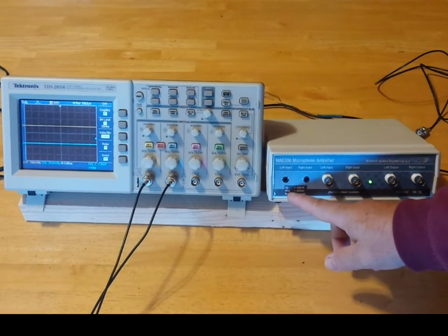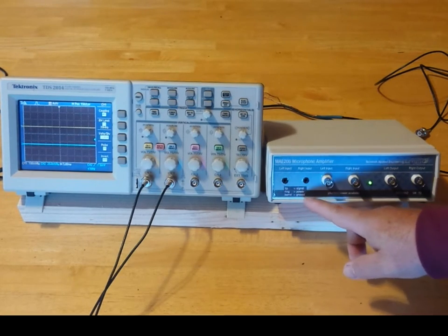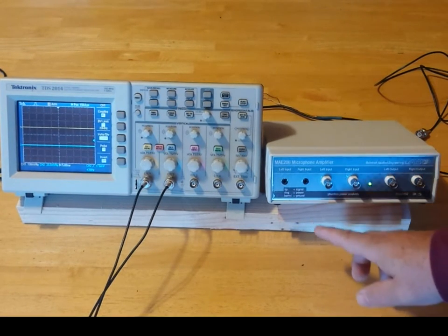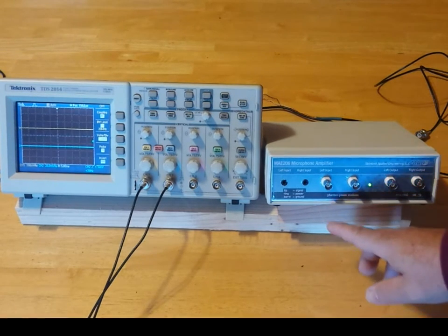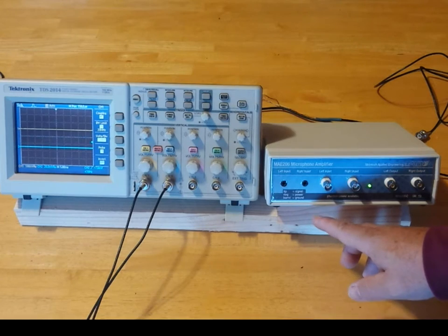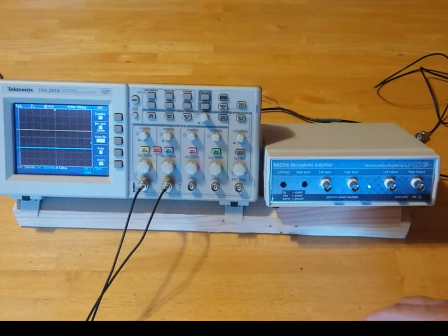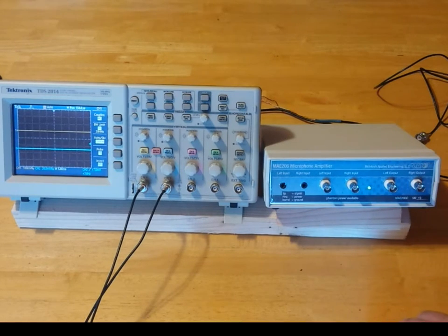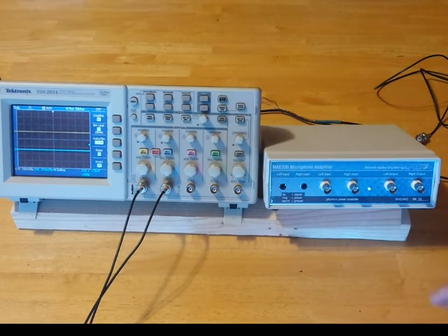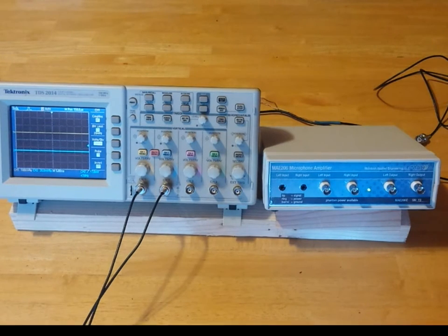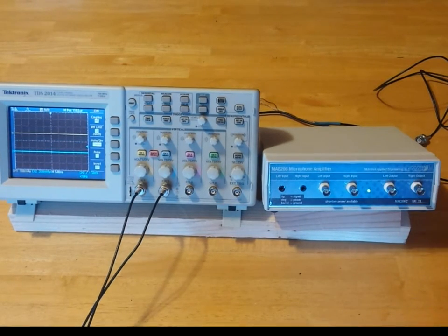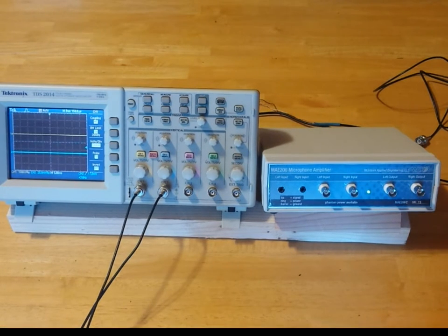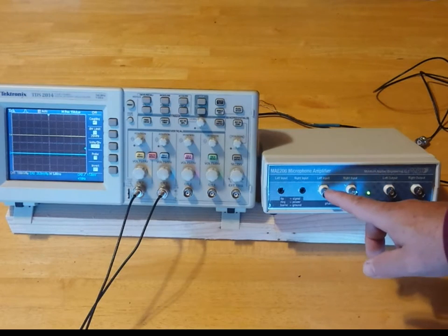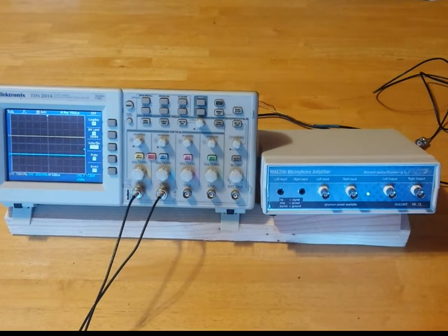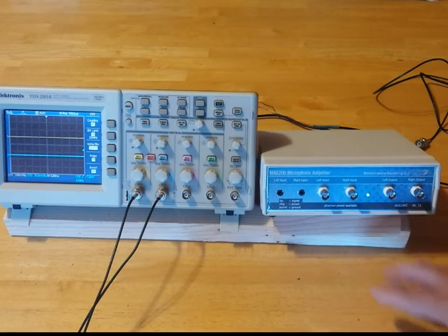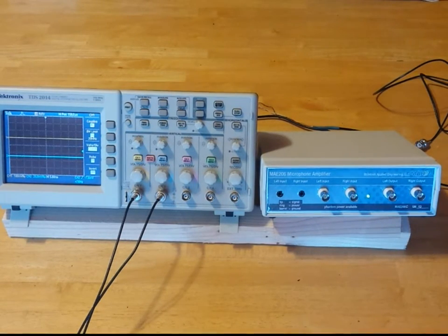The first input is a 3.5 millimeter stereo connector, where the three pins on that stereo connector are used for a microphone, where one of the connections is for signal, the other is for the power, and then the third is for ground. So that's something that's typically found in an analog MEMS microphone. These BNC inputs are used for pretty much any other single-ended signal. A phantom supply can also be selected for these inputs so that you can run an electret microphone directly off of the inputs to this microphone.